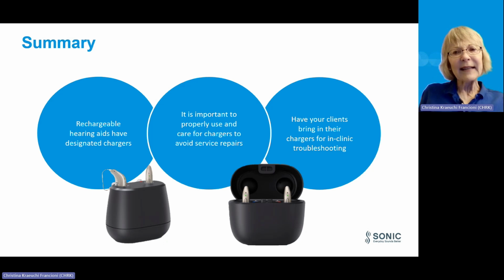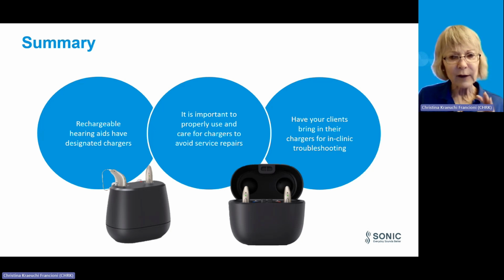Now I would like to end this webinar with 3 points for you to remember when you start troubleshooting Sonic rechargeable hearing instruments. First, each hearing aid style has a designated charger which depends on the platform of the hearing aids and should only be used with that specific charger.